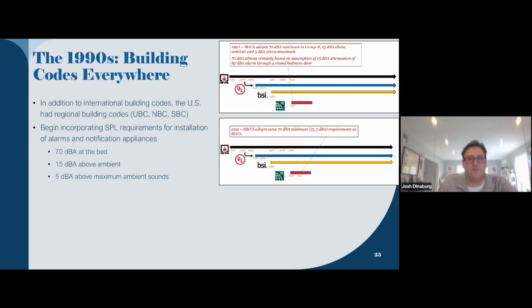Now in the 90s, if anybody's familiar with how building codes worked back then, there were all kinds of regional building codes in addition to the national ones. And they all started bringing in some of these requirements. So we get BOCA bringing in 70 dBA with this 15 above ambient, 5 above the maximum. We're getting 70 dBA really based on recommendations that you lose about 15 decibels going through a door - so if you've got 85 in the hallway, you'll get 70 in the bedroom. So kind of tying together the installation standard with the device standards.